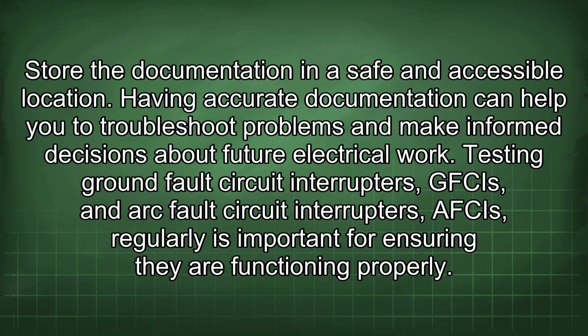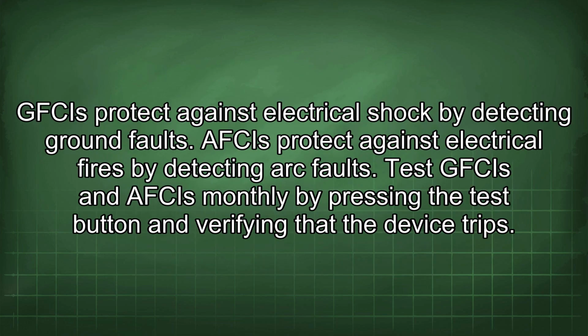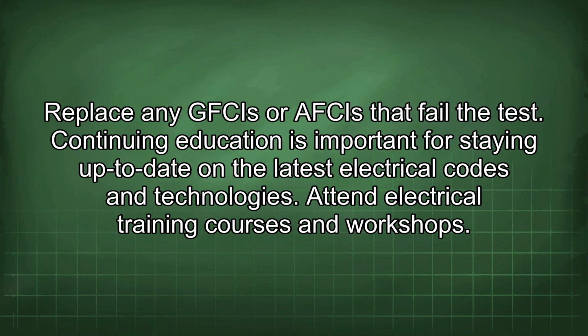Testing ground fault circuit interrupters, GFCIs, and arc fault circuit interrupters, AFCIs, regularly is important for ensuring they are functioning properly. GFCIs protect against electrical shock by detecting ground faults. AFCIs protect against electrical fires by detecting arc faults. Test GFCIs and AFCIs monthly by pressing the test button and verifying that the device trips. Replace any GFCIs or AFCIs that fail the test.